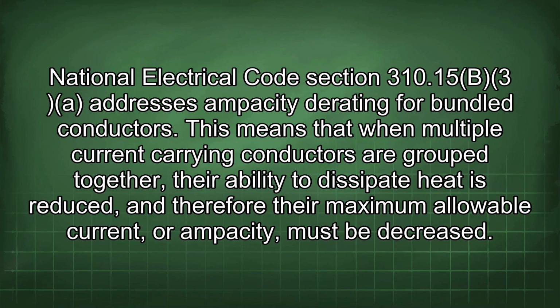National Electrical Code Section 310.15(B)(3) addresses ampacity derating for bundled conductors. This means that when multiple current-carrying conductors are grouped together, their ability to dissipate heat is reduced, and therefore their maximum allowable current, or ampacity, must be decreased.